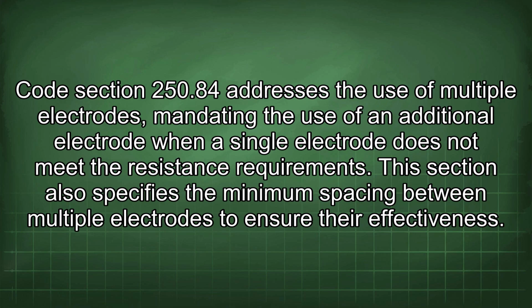Code section 250.84 addresses the use of multiple electrodes, mandating the use of an additional electrode when a single electrode does not meet the resistance requirements. This section also specifies the minimum spacing between multiple electrodes to ensure their effectiveness.